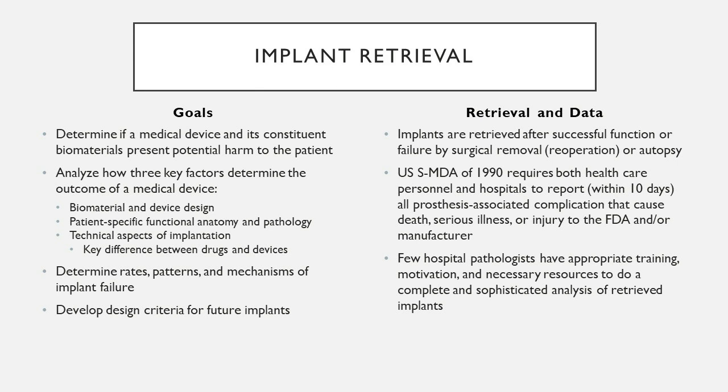Now, the implant retrieval process provides an opportunity to identify the modes, interactions, and mechanisms that lead to the success or failure of a medical device under end-use conditions. Now, the latter is particularly important because this is information that we can't get from just a benchtop setting. This is not a bulk, surface, or material property of that particular device.